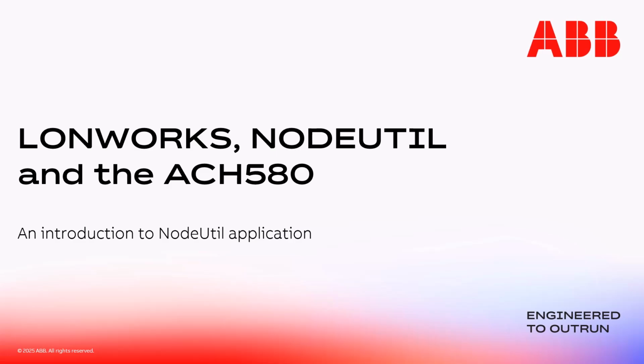Jeff Brunner here with the ABB HVAC Drives Applications Engineering team, and in this video I would like to go over how to connect to an ACH580 with Lonworks using the FLON module. In particular, I would like to introduce the NodeUtil application, which is a PC-based tool. It's free, and it's used to connect into a Lonworks network to do basic device discovery, configuration, and control.